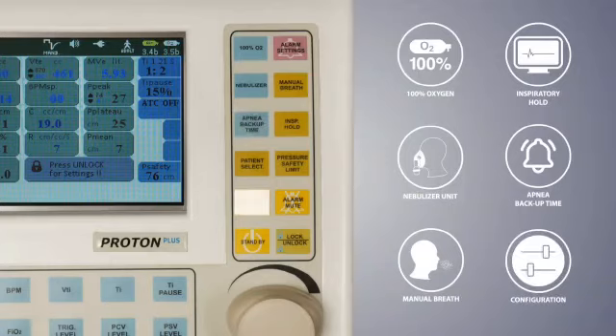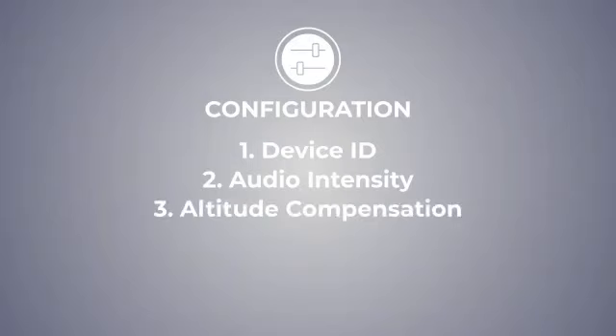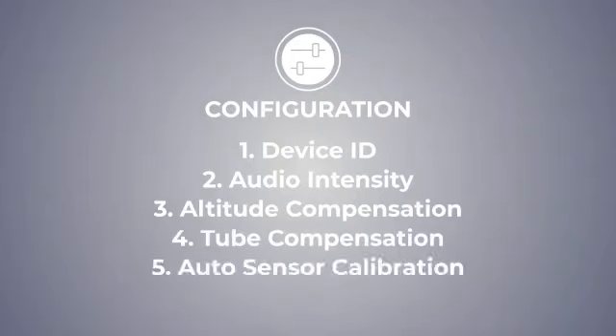Configuration: Device ID is used to give the device number. Audio intensity is to increase or decrease the volume of alarm. Altitude compensation is used to compensate the altitude. Tube compensation is used to compensate the dead space of endotracheal tube or tracheostomy tube. Auto sensor calibration is used to calibrate FiO2 sensor when required.